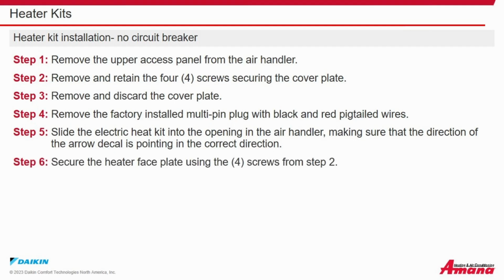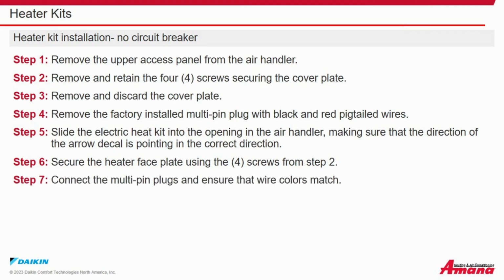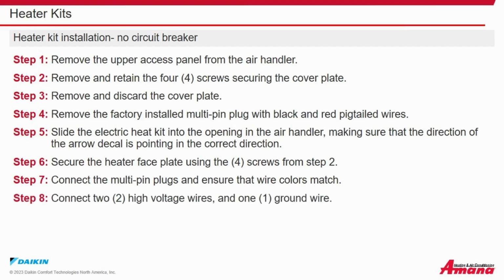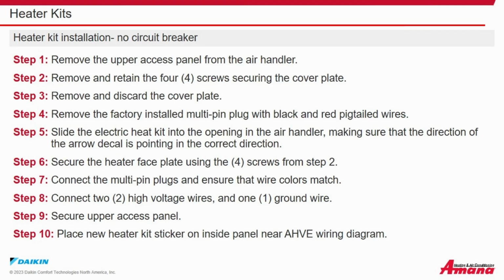Step 6. Secure the heater faceplate using the 4 screws from Step 2. Step 7. Connect the multi-pin plugs and ensure that the wire colors match. Step 8. Connect 2 high-voltage wires and 1 ground wire. Step 9. Secure upper access panel. Step 10. Place the new heater kit sticker on the inside panel near the AHVE wiring diagram.